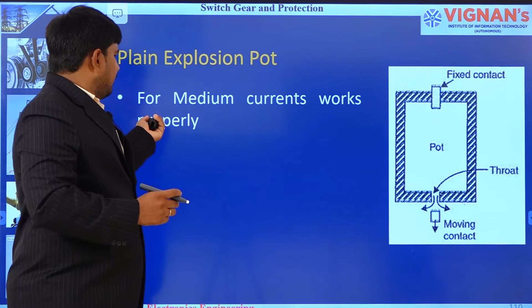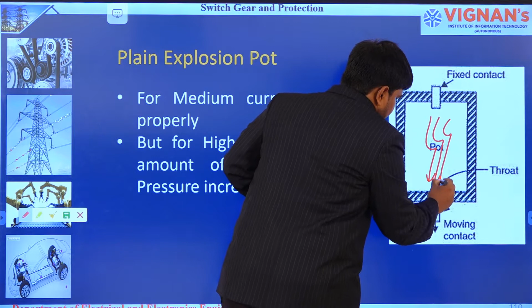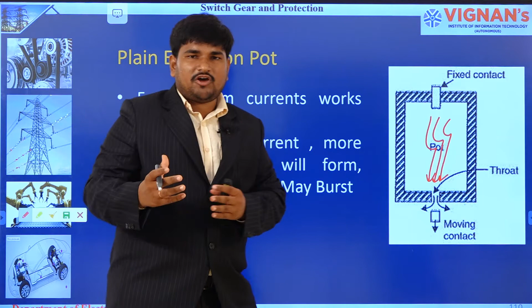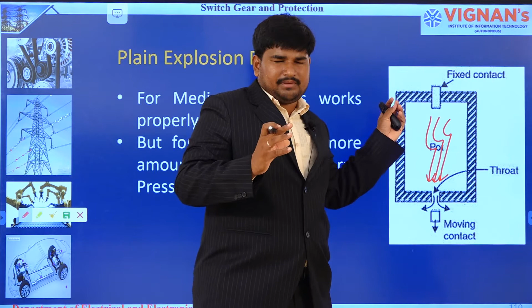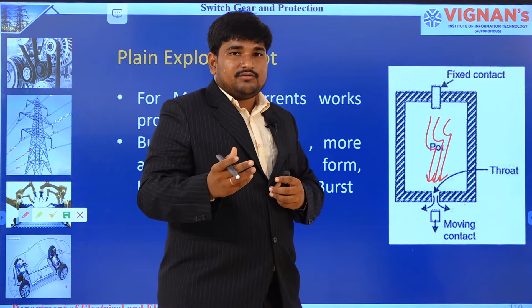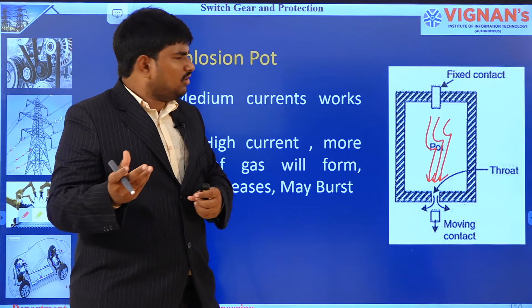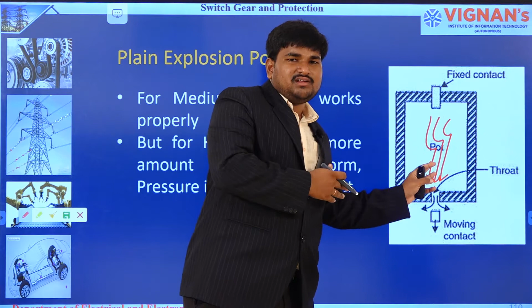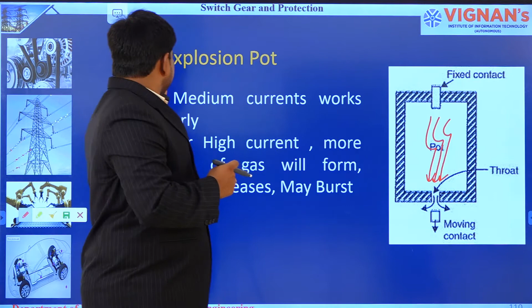This is only used for medium currents. Why? Because, for example, let us take higher currents. In higher currents, a high amount of arc is produced here. This high amount of arc ionizes and heats up the oil, so more hydrogen gas will be produced inside this chamber. Hydrogen has explosive characteristics, so because of the pressurized hydrogen, the total chamber can be blasted. This happens because we are using it for higher currents. That is one drawback of the plain explosion pot.